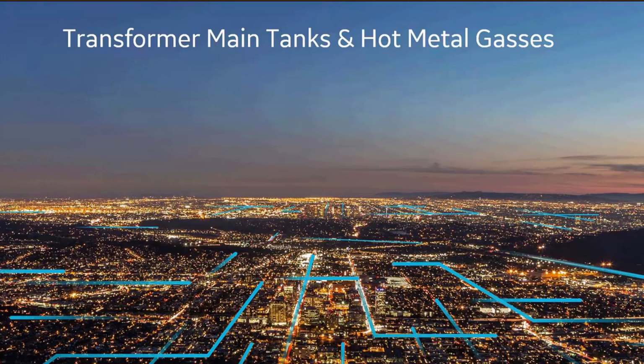As we've discussed on other calls, the thing we looked for back then was primarily whether we had acetylene in the transformer, because of all the things we knew we shouldn't have, we knew we shouldn't have acetylene. So folks think of arcing, they think of acetylene, and if your transformer tripped out on differential operation, well, one of the first things you wanted to know was: do I have acetylene in the transformer? That was kind of most of our introduction to DGA.